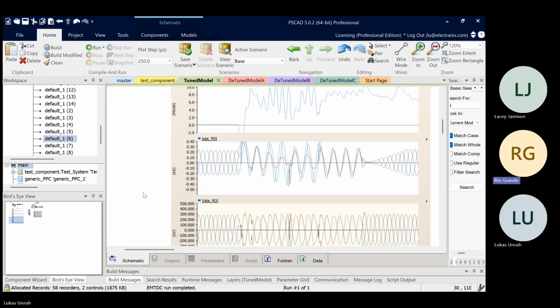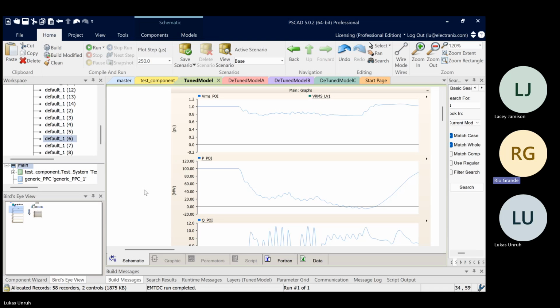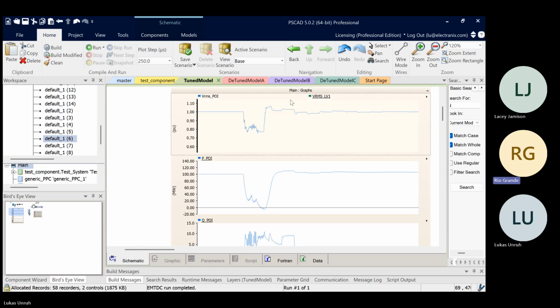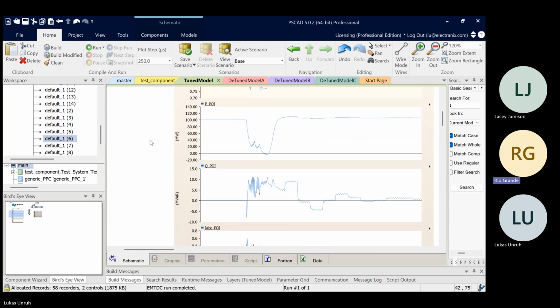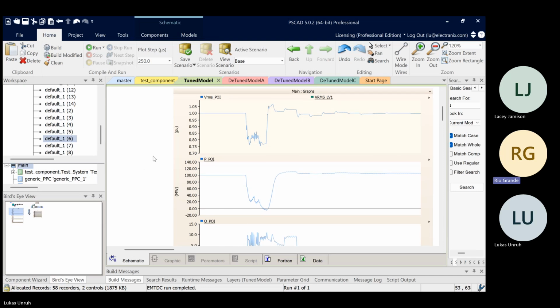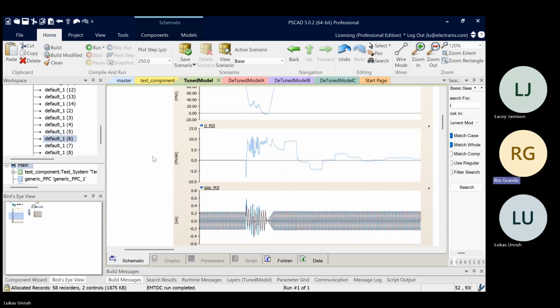It may or may not be a problem during the fault, right? After the fault, it might recover very quickly and not cause any issues. But yeah, I don't know. We definitely would prefer to see a straight line here, obviously, but it may or may not be something that you're going to put up a big fight about, depending on the circumstance.